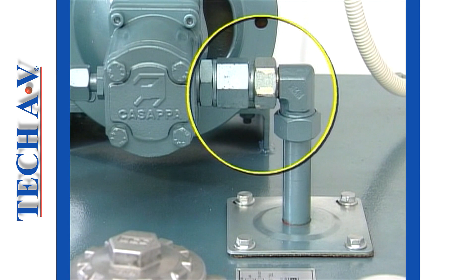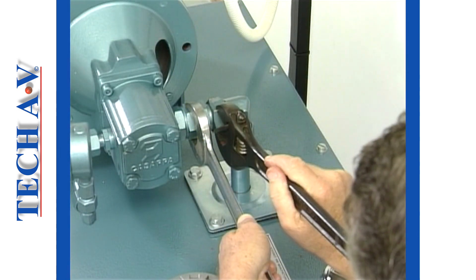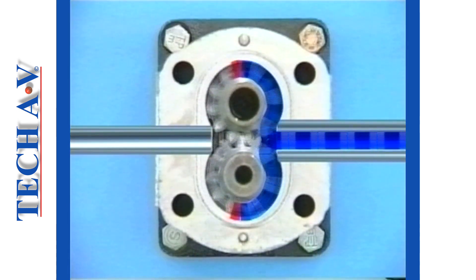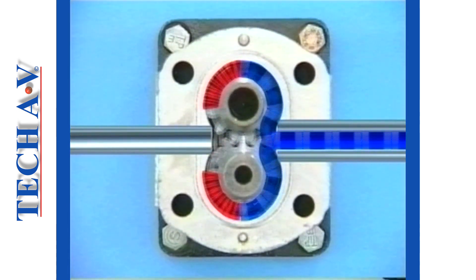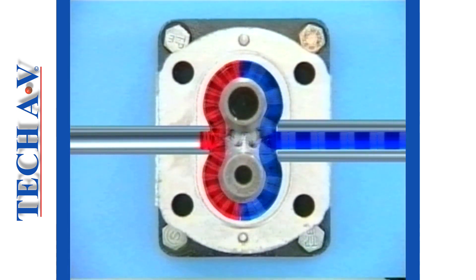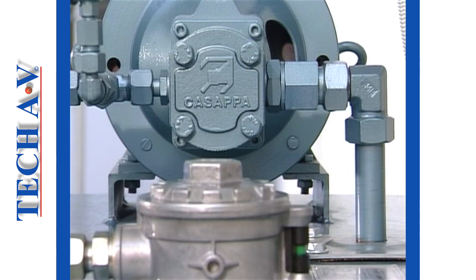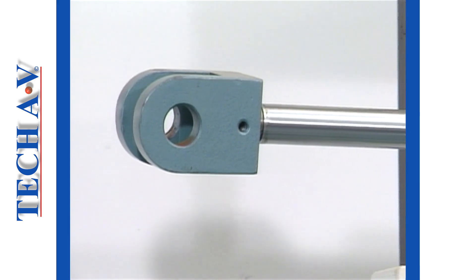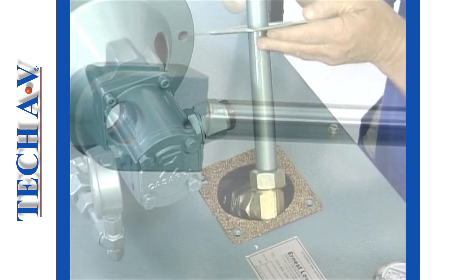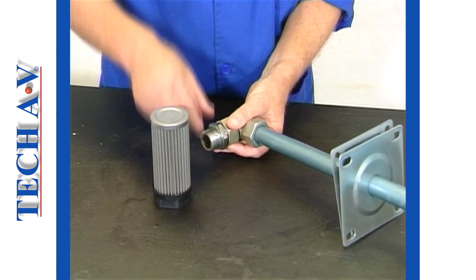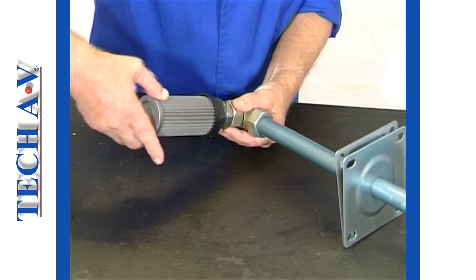Next, check and, if necessary, secure any loose connection on the pump suction line. A loose connection at any one of these connections is a common cause of pump and delivery related problems. If the problem on your system involves a noisy pump and a lack of power and speed in the actuators, then you should inspect the suction strainer and clean or replace it as described in Module 2 of this series.